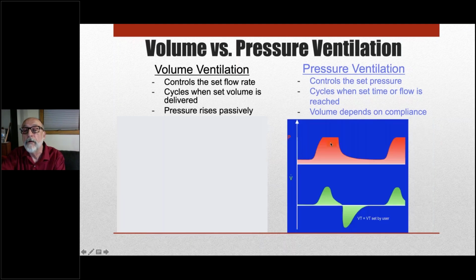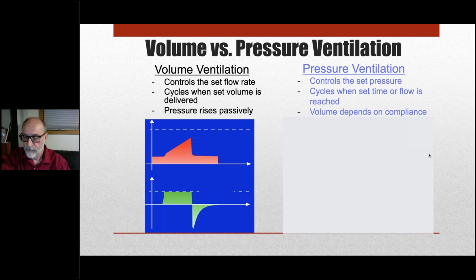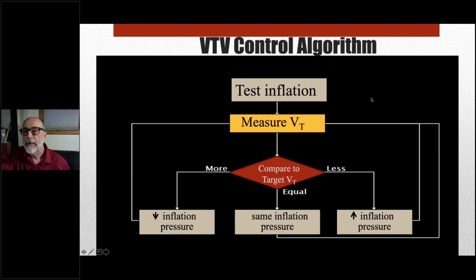So volume targeted ventilation, volume guarantee, is pressure control with volume targeting. Many authors refer to all forms of ventilation that attempt to control tidal volume in some fashion as volume targeted. But I think that causes confusion, and I think we need to keep them distinct, because what volume guarantee and related modalities on some other devices are really pressure controlled ventilation with volume targeting, different flow pattern. And the control algorithm has become similar in different devices, although they're not all the same. And I will talk about some of the specific advantages of the Dräger device. But in principle, they all begin with some form of pressure delivery.